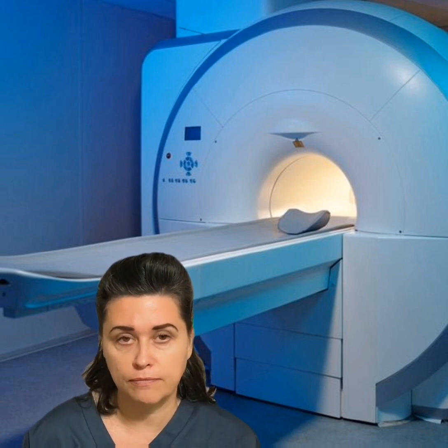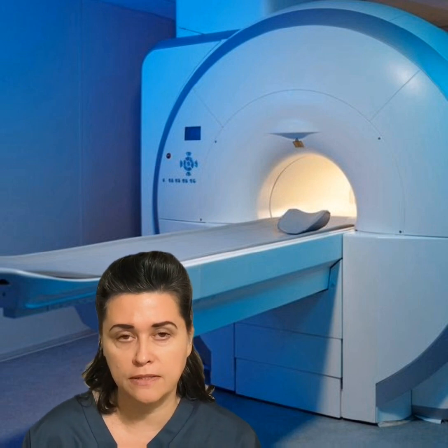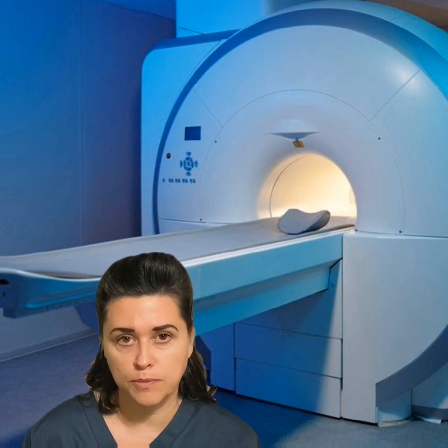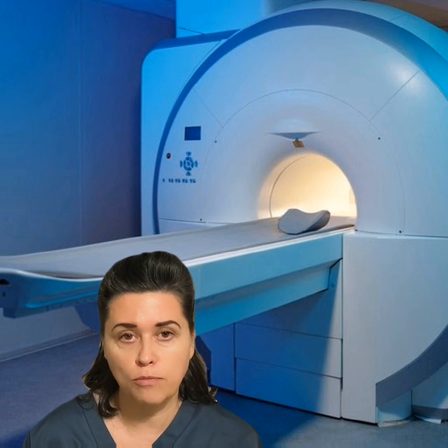Room temperature has to be monitored by staff on a regular basis. Cryogen levels have to be monitored, especially for superconductive scanners, and the industry acceptable number is that 75% of cryogen has to be present. If the number goes down, it has to be taken care of as soon as possible. Transmitter gain attenuation is, simply put, the ability of the scanner to know exactly how much RF energy is needed to produce a 90-degree flip angle or whatever angle needs to be produced.